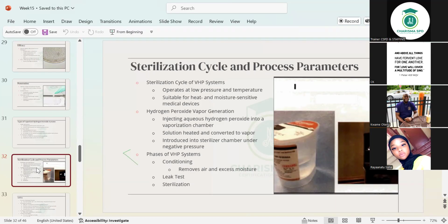Okay. And then the phase is just like what we did before. It goes through the conditioning where it removes the air and excess moisture. It goes to the leak test where if there is a leak, it's rather going to suck air from outside into it instead of releasing air from it out to come out. Okay. And then the sterilization.